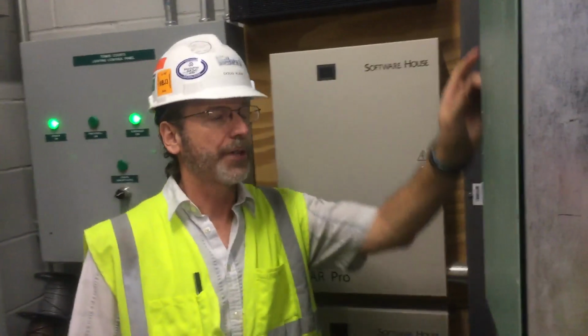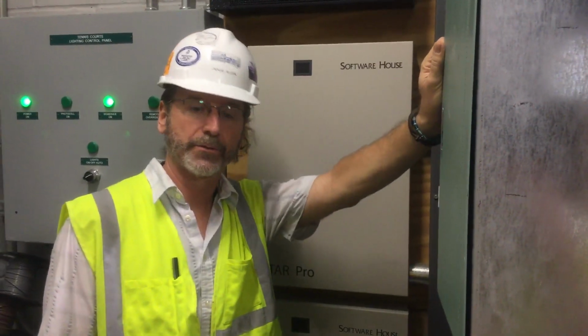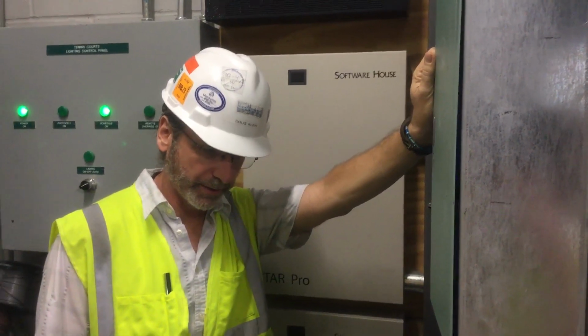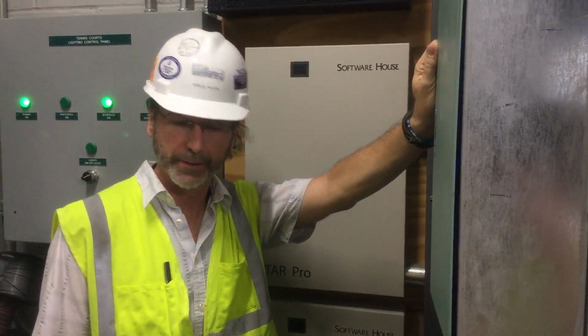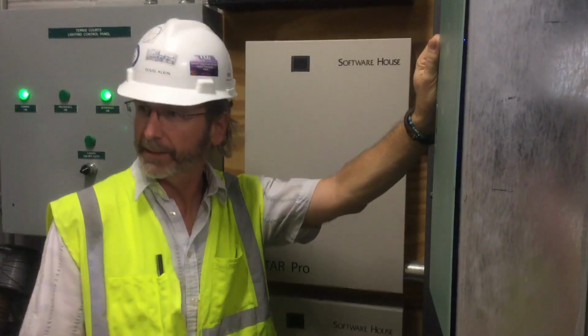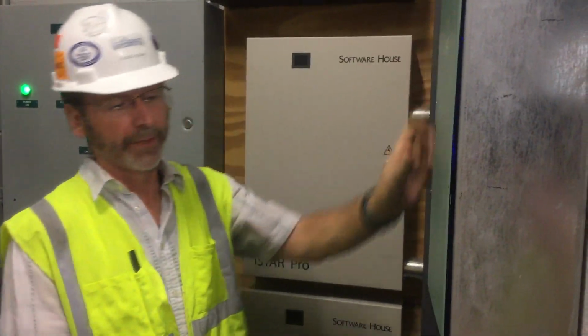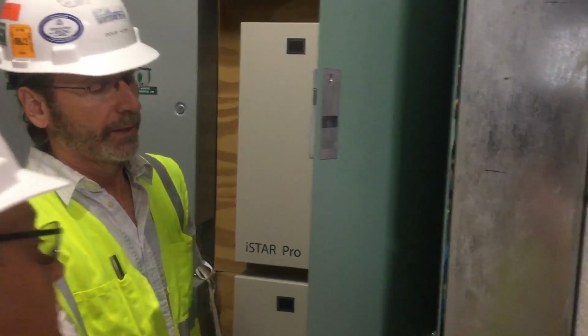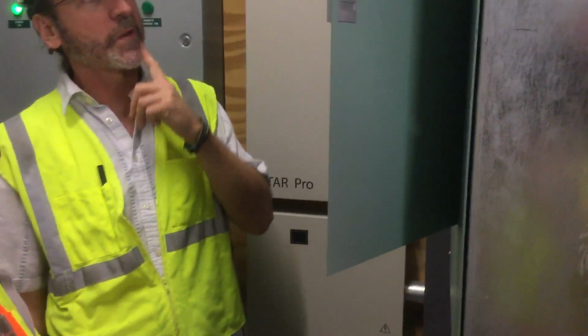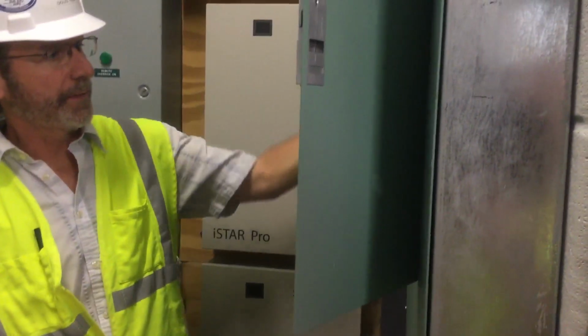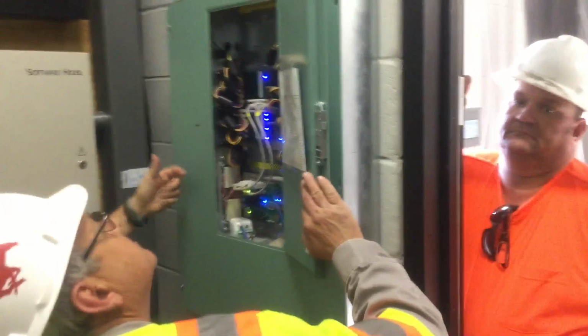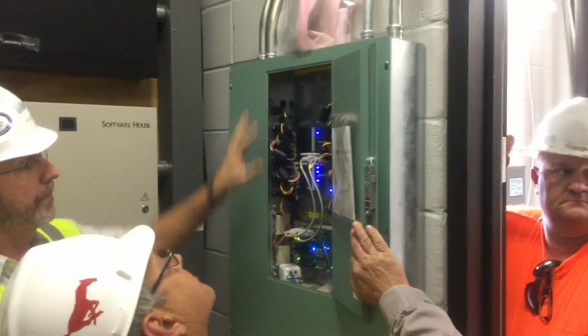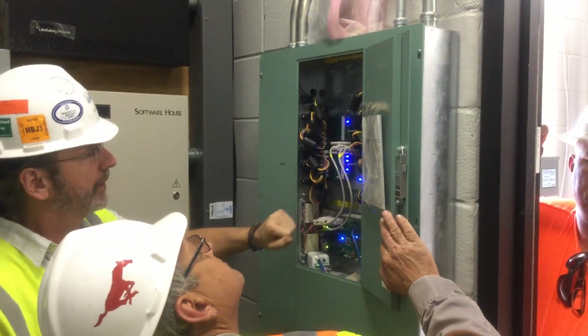Okay, I'll talk now about the relay panel that controls the lighting inside the lacrosse field building, and also a couple of site lighting circuits. This is a pretty standard Watt Stopper relay panel—you're probably familiar with these. There are high voltage relays down the left and right hand sides, and a power supply transformer right here that's fed with a hot circuit. When this transformer is powered up, it powers up the electronics inside the panel.